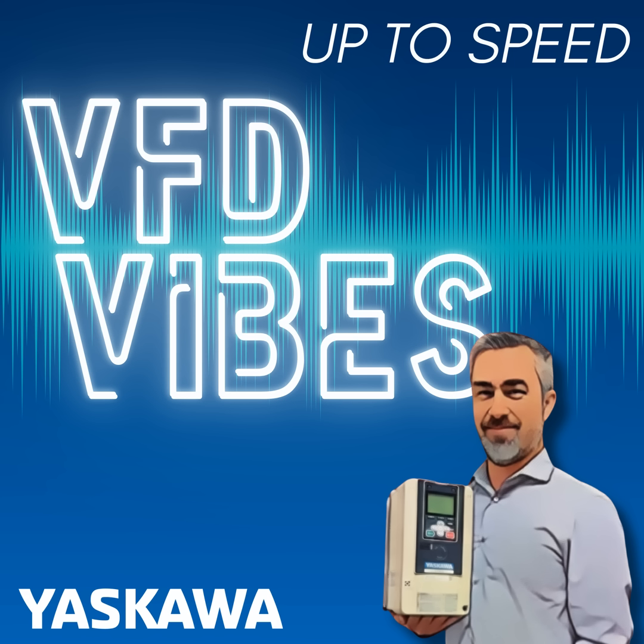Well, it turns out the electric heating actually dampened the voltage distortions. Electric heaters are not a harmonics mitigation tool by any means. However, in this particular case, running the electric heating smoothed out the voltage distortions and allowed equipment to work as it should. As soon as the electric heating was shut off, the harmonic currents and the resulting voltage distortions presented themselves, and the LED lights wouldn't turn on, and the instrumentation didn't function correctly. So this customer had to install additional harmonic mitigation to make the system work under all conditions.